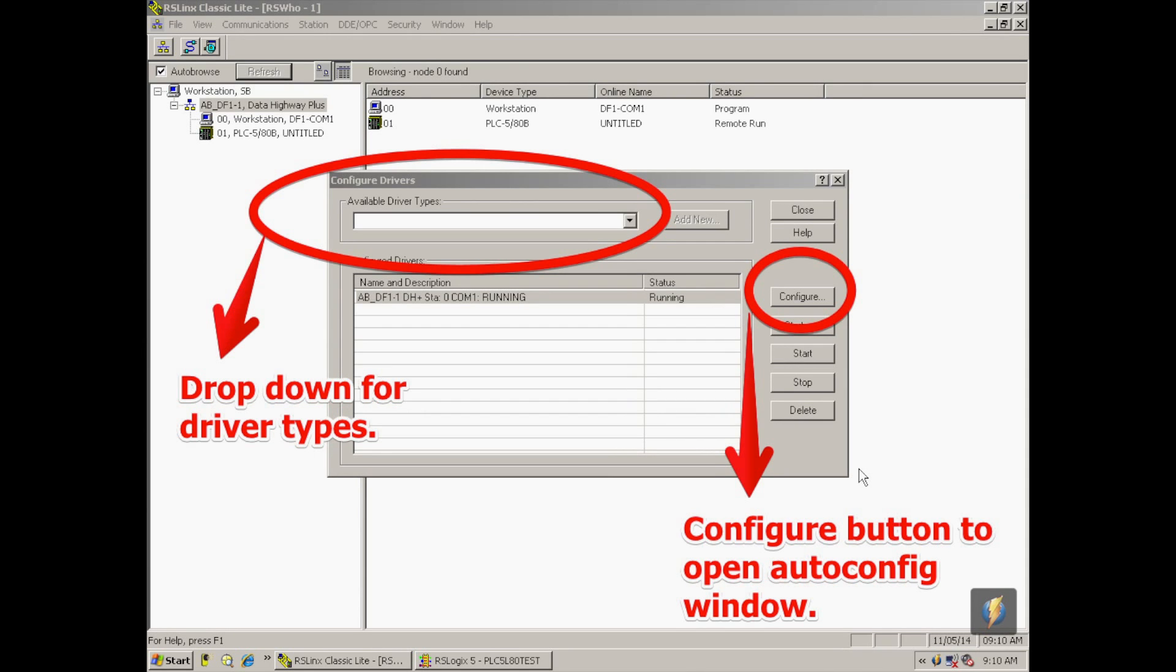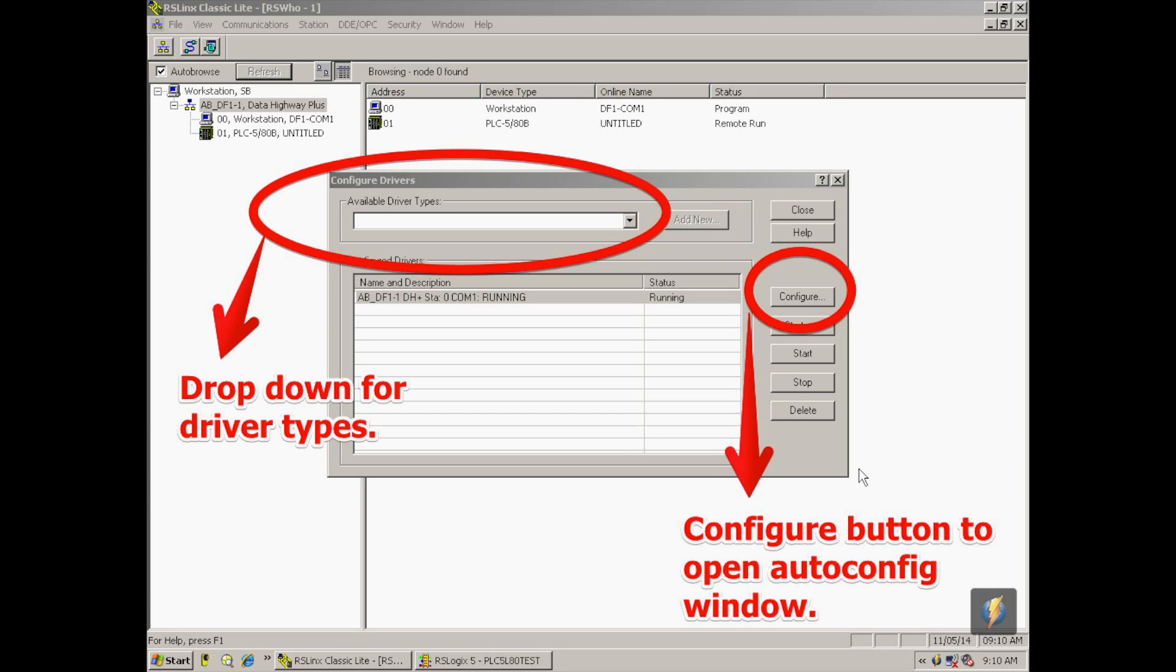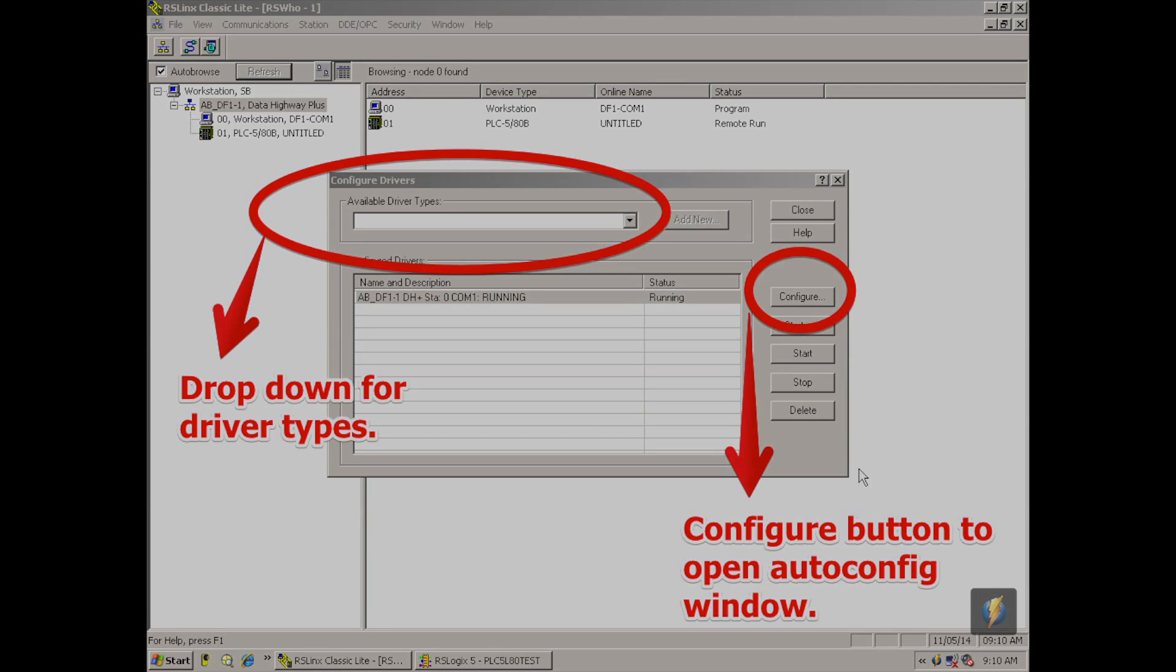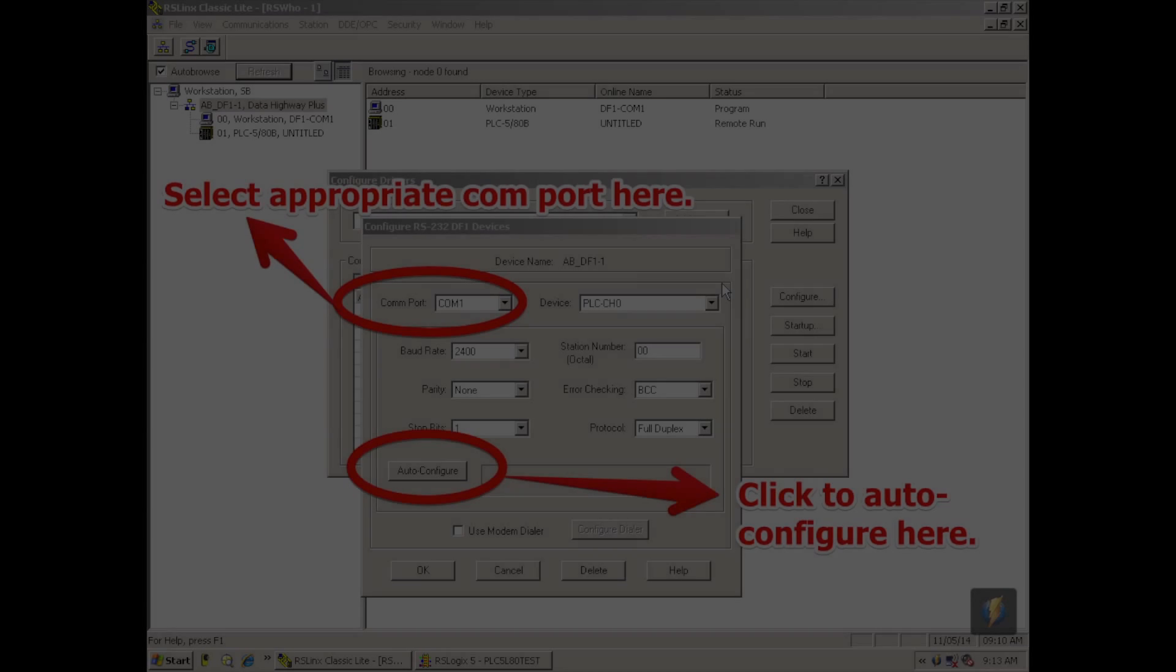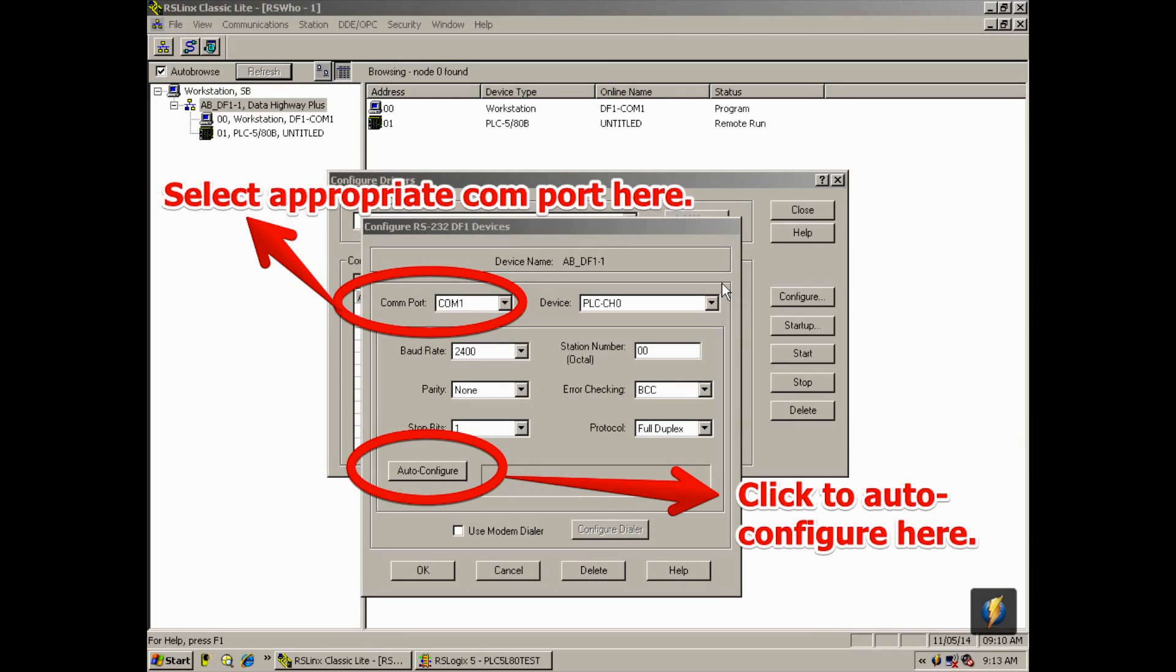And a third window will pop open. It says configure, in this particular case, RS-232 DF1 device driver. And I'm going to select auto configure. We call it the cheat button. And it will go ahead and change any of the, as long as you're on the right communication port, it will go ahead and change baud rate, parity, stop bits, device type on its own. That's why we call it a cheat button. So once that says auto configuration successful, I'm going to click okay.